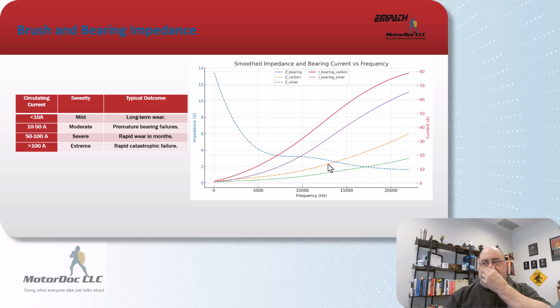And as you can see, the amount of current flowing, if this was based on 100 amps measured on ground, at 22 kilohertz, I still have some current flowing through the brushes at about 20 amps versus 80 amps going through the bearing, or just shy of 70 amps. But I'm still dealing with a severe problem in which I'm going to have degradation in this bearing relatively quick.